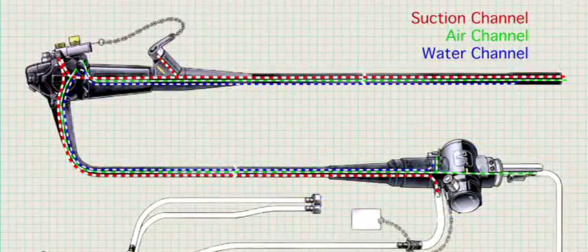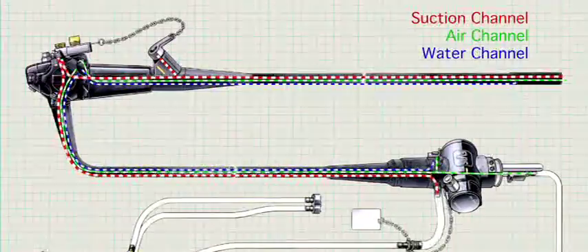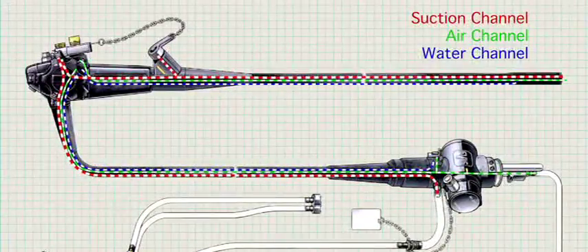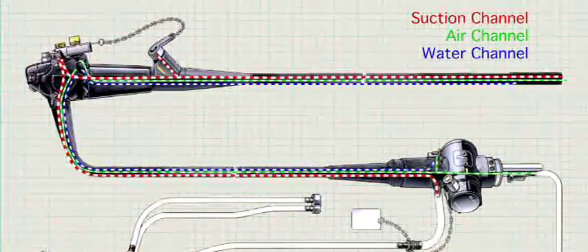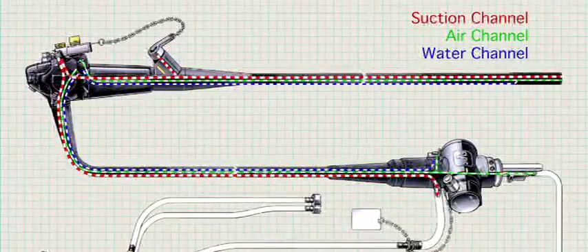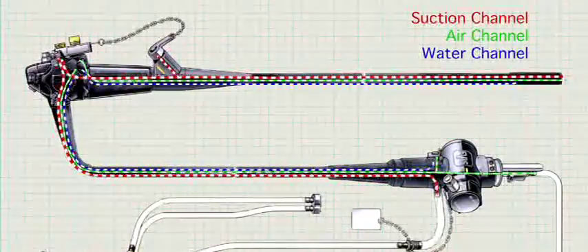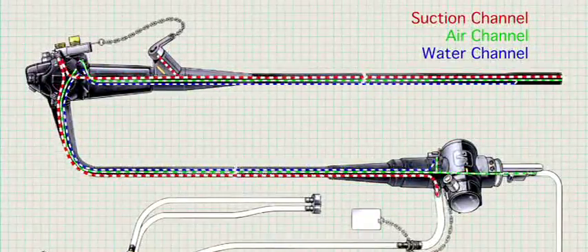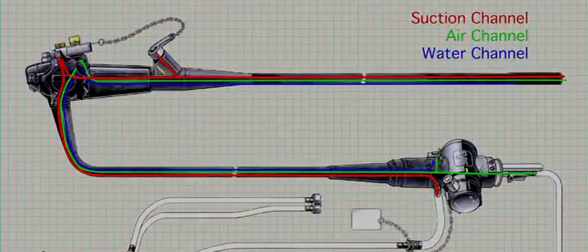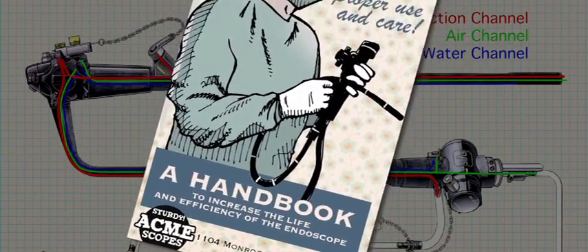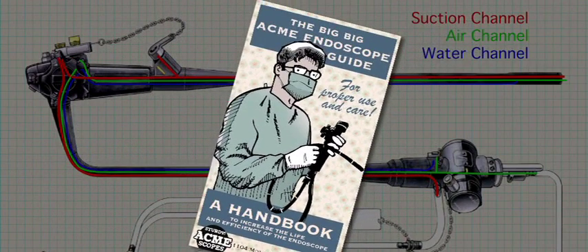Use a cleaning brush for all channels that are accessible. Purge all other channels such as air or water channels. Some scopes have special feature channels such as elevator wire and auxiliary water channels that must be accessed during reprocessing. Refer to the endoscope manufacturer's instructions for information specific to each brand and model of endoscope. Several brands will be used in this presentation to illustrate special features.